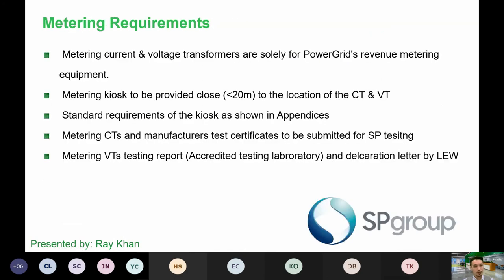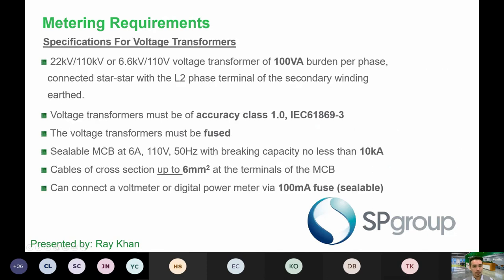All right, so I've listed down some of the key requirements in terms of the metering requirement. Metering current and voltage transformers are solely for power grid revenue metering. Metering kiosk provided close below 20 meters. Location of the CTs and VTs. Standard requirements are the kiosks, metering CTs, and manufacturer test certificate to be submitted for SP power grid testing. The metering VTs testing report, accredited testing laboratories and declaration letters also by the LEW.